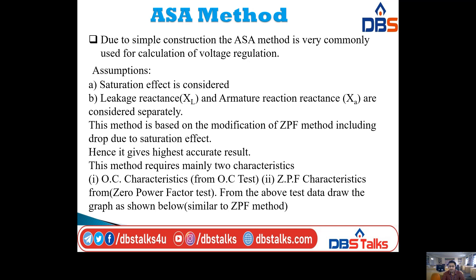The ASA method includes the drop due to saturation effect, hence it gives the highest accurate result. The ASA method requires mainly two characteristics similar to the ZPF method: the OCC characteristics from the open circuit test and ZPF characteristics from the zero power factor test. From this test data, a characteristic diagram can be drawn consisting of the OCC curve and ZPF curve, with the Potier triangle in between.